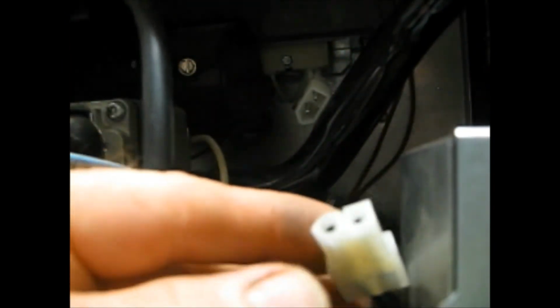If you ruled out your pressure switch, the next thing to test is your hot surface igniter, which is back in there. It's that white porcelain thing. And there's a plug right here where you can unplug this. So this is a plug that leads to your hot surface igniter. So what we're going to do, we're going to put our voltmeter inside here and see if we have power when it's time to ignite.